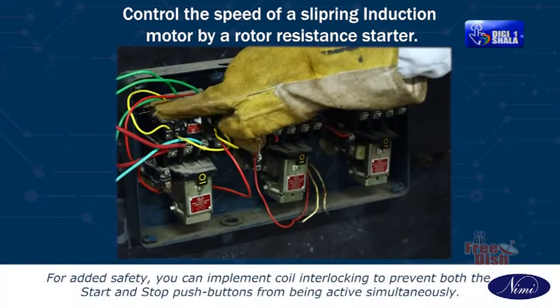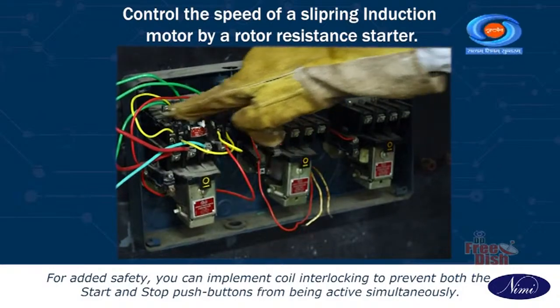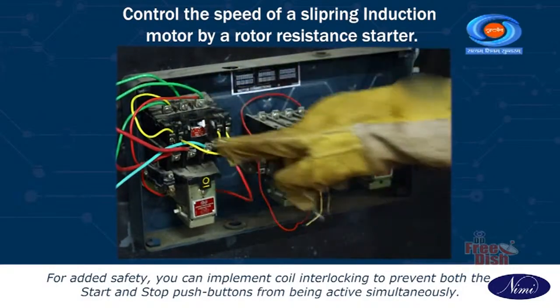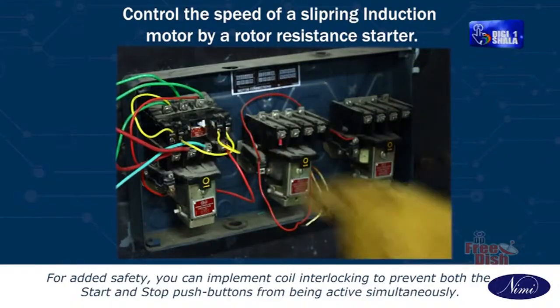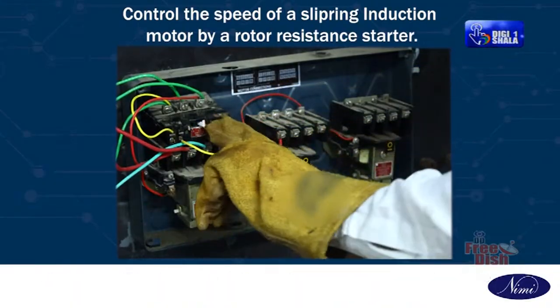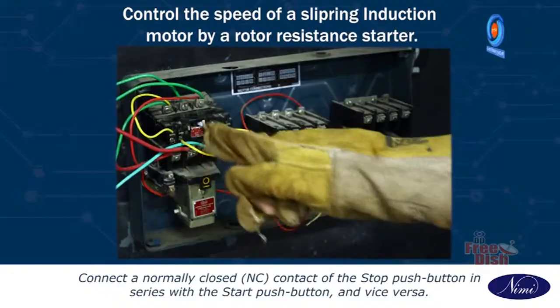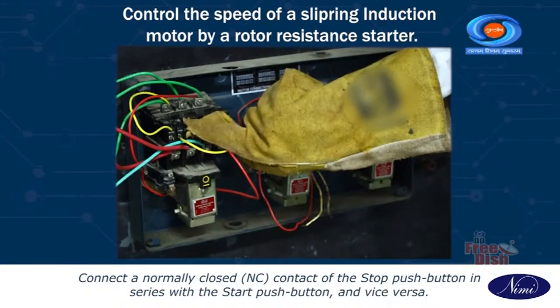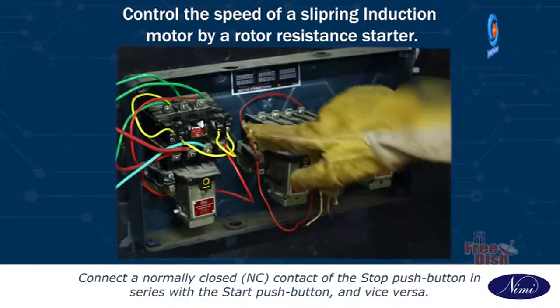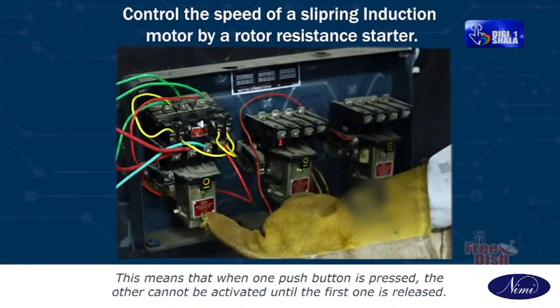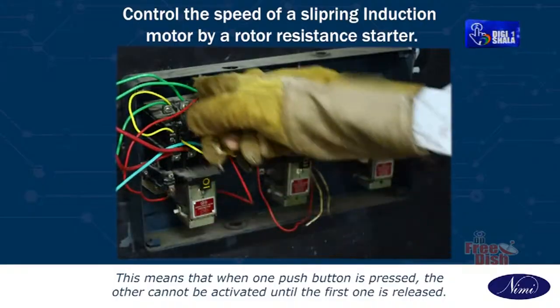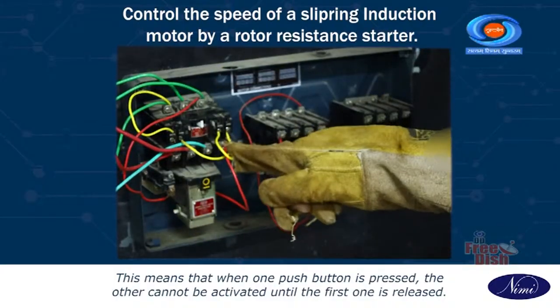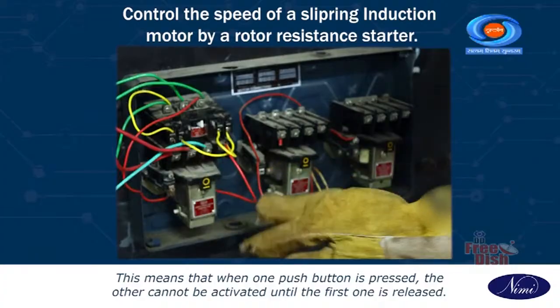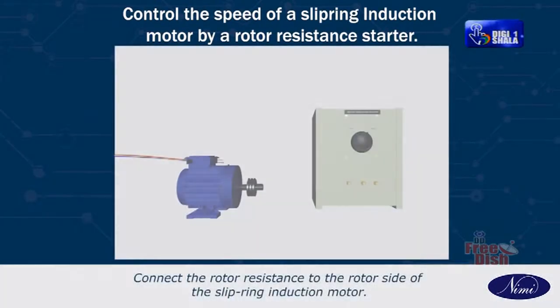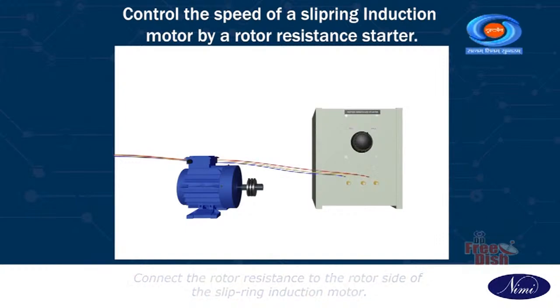For added safety, you can implement coil interlocking to prevent both the start and stop push buttons from being active simultaneously. Connect a normally closed contact of the stop push button in series with the start push button and vice versa. This means that when one push button is pressed, the other cannot be activated until the first one is released. Connect the rotor resistance to the rotor side of the slip ring induction motor.